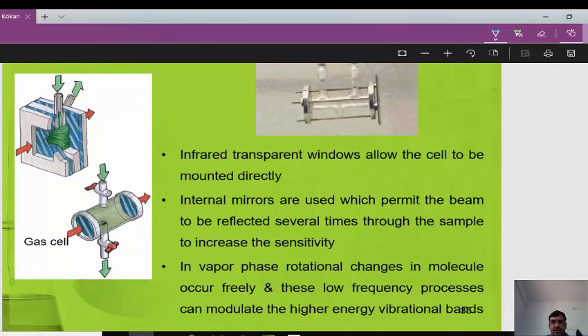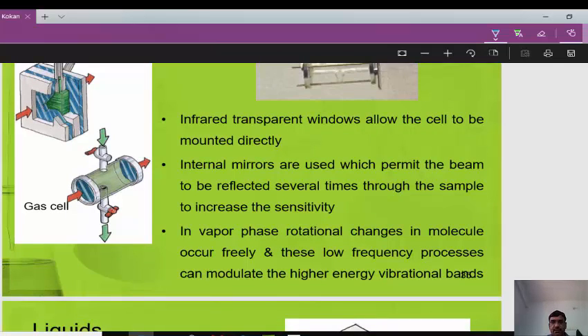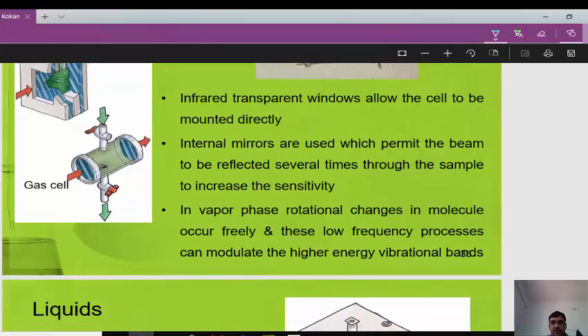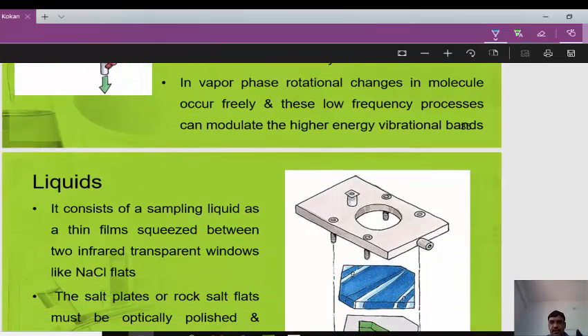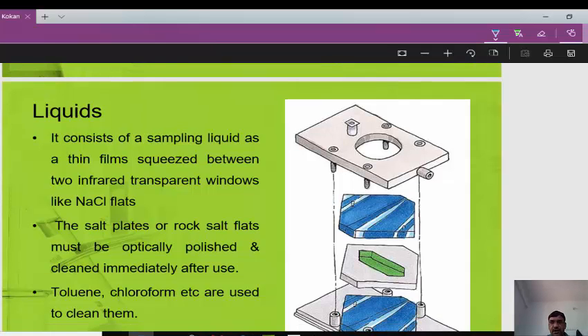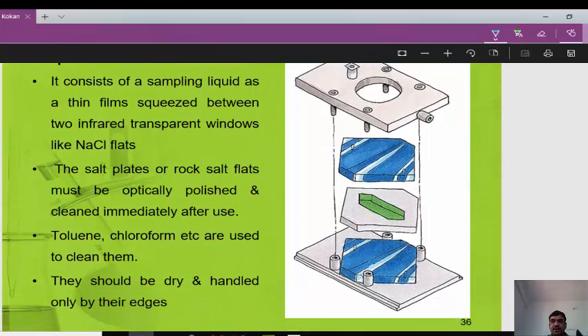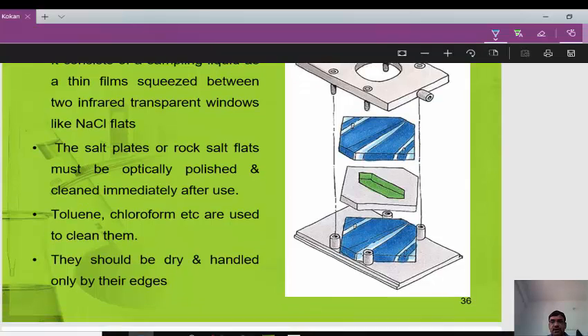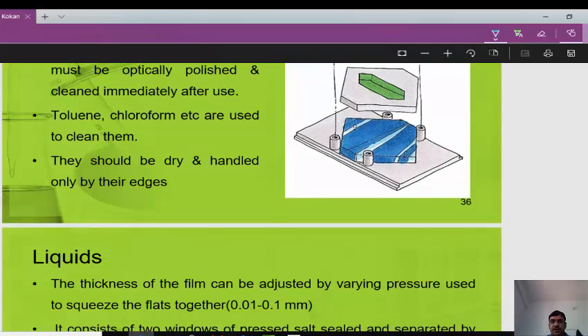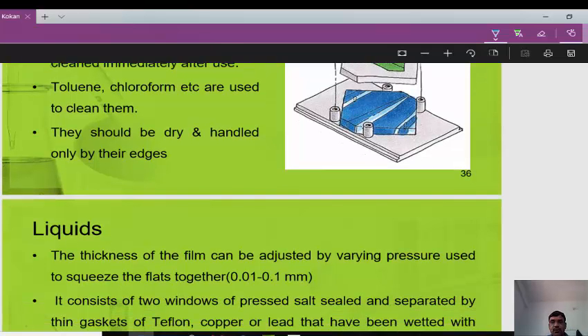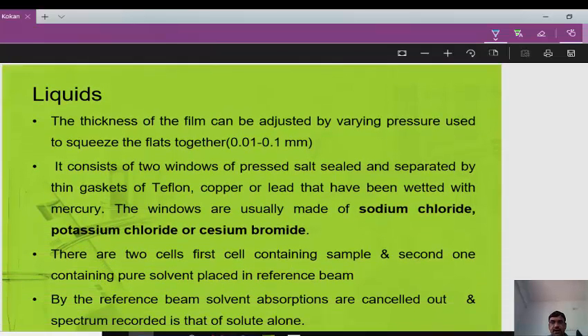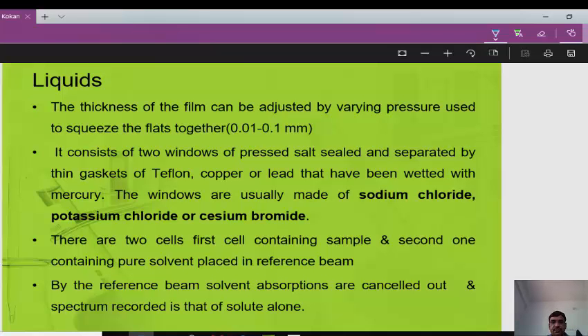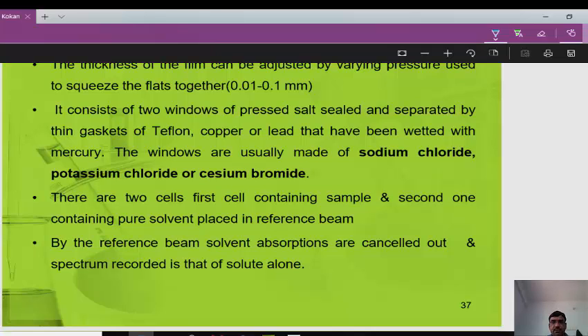Sample handling in IR depends on whether the sample is a gas, liquid, or solid. For solids, KBr discs are used; for liquids, thin films; for gases, gas cells are used. Gas cells have infrared-transparent windows and internal mirrors that reflect the beam multiple times through the sample to increase sensitivity. In the vapor phase, rotational changes occur freely and can modulate higher-energy vibrational bands.